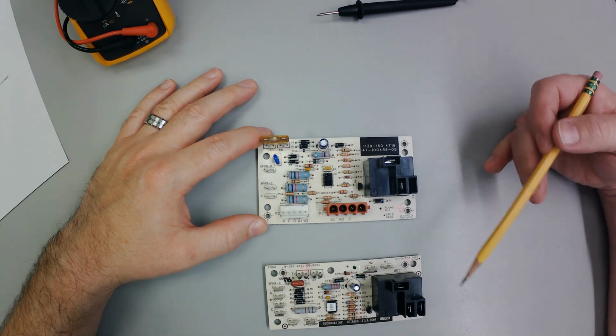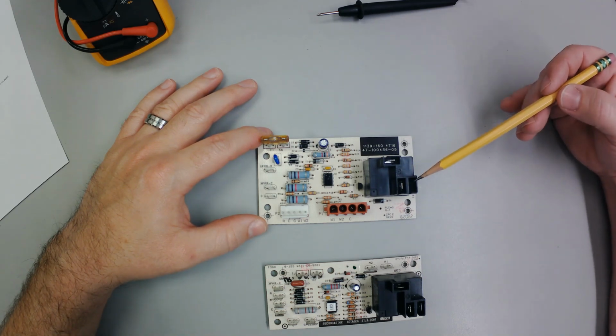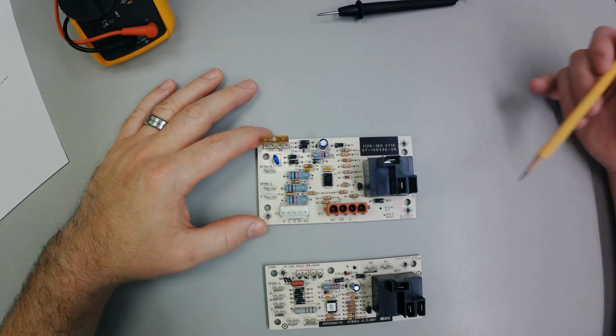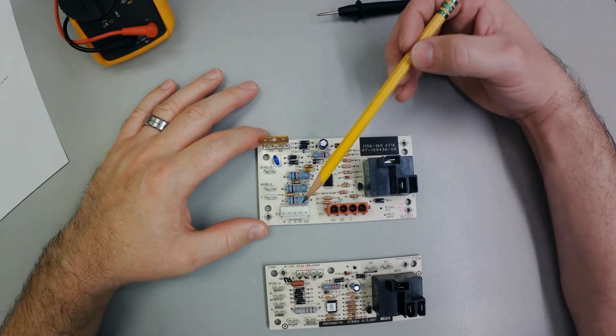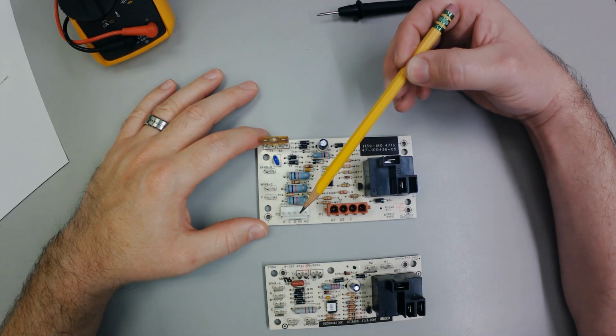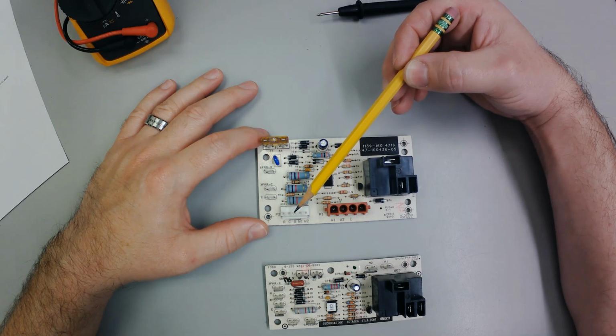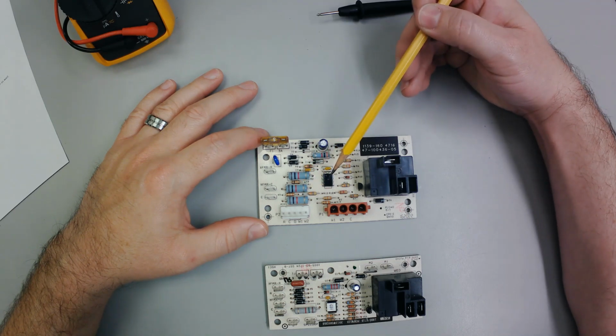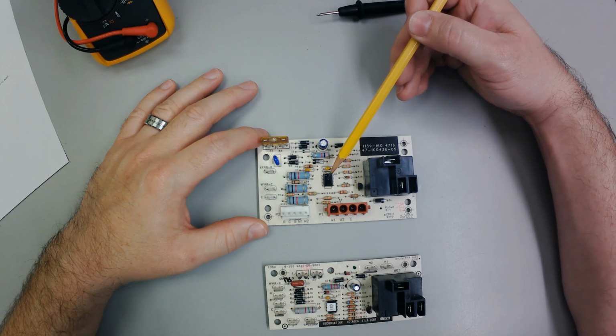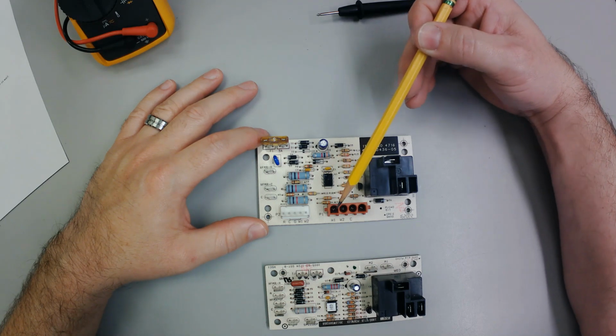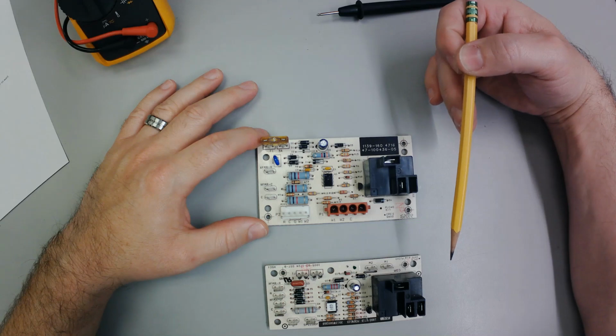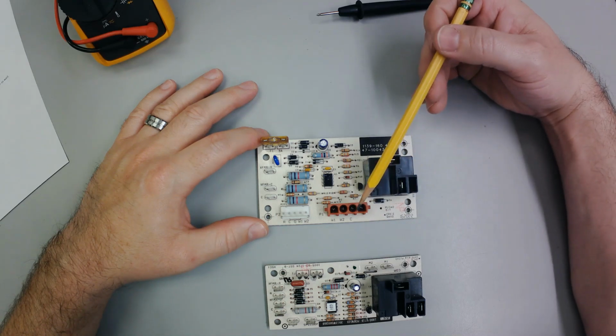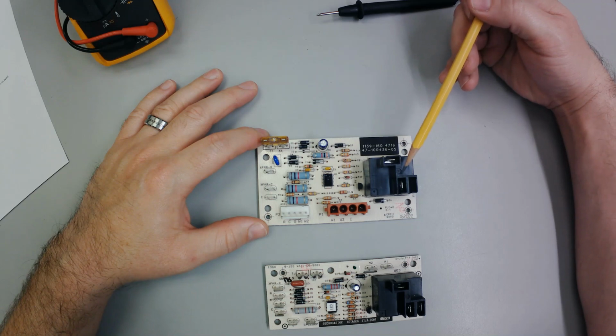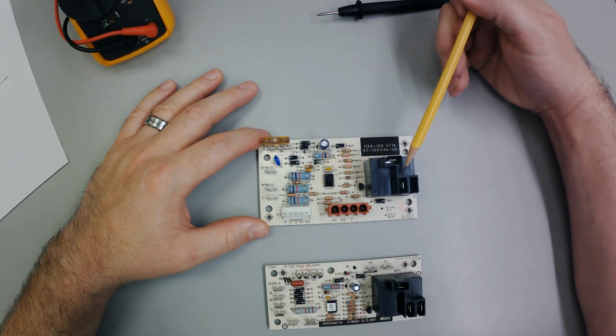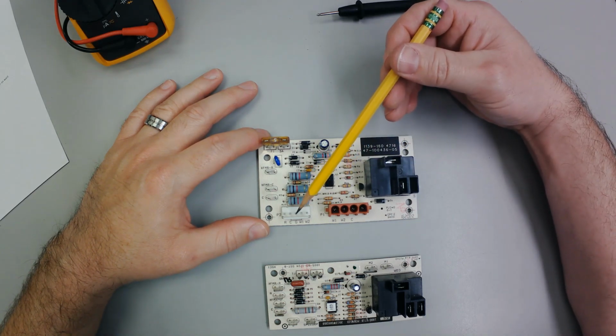The circuit is closed. It's complete already. This relay doesn't have it. And for my simple little thinking, it's because anytime power comes in on this W1 or W2, whether I have a call for the fan on the G circuit or not, this brain knows that when I send power out to the heat sequencer or contactor or whatever, I'm going to turn on the fan with it. I don't need a normally closed on this relay because it doesn't matter if I've energized G or not.